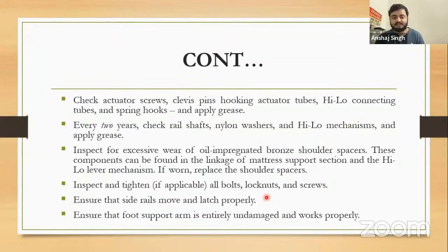Every 2 years, check rail shafts, nylon washers, and high-low mechanisms and apply grease. Inspect for excessive wear of oil-impregnated bronze shoulder spacers. These components can be found in the linkage of mattress support section and the high-low lever mechanism. If worn, replace the shoulder spacers.